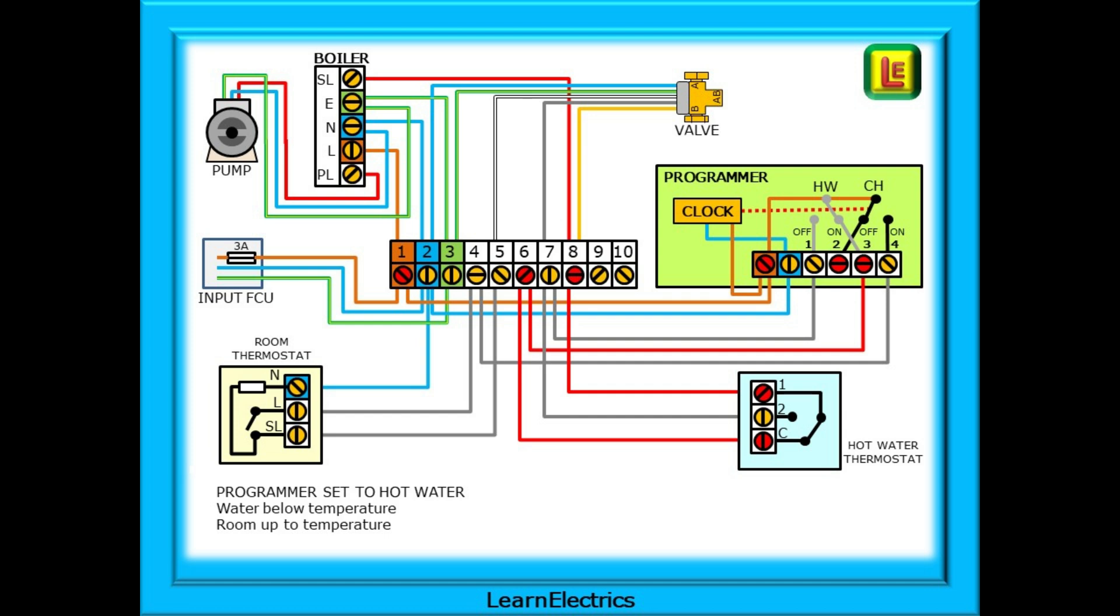At some point the water temperature has dropped. The water thermostat has changed contact positions. Common is now connected to one. The 240 volts on C passes to terminal one and back up to wiring center number eight. Through eight to the boiler and turns the boiler and pump on. Because terminal two in the water thermostat is not connected to C, it loses the 240 volts, and as a result wiring center seven falls to zero volts, and this enables the valve to connect AB to B and permits water flow to heat up the water cylinder.